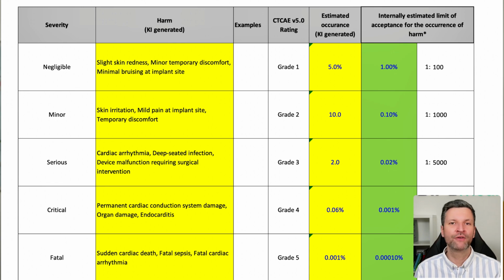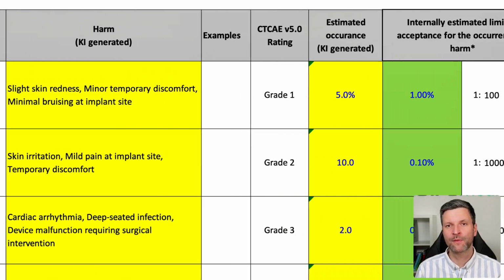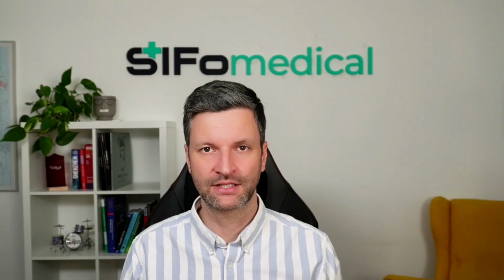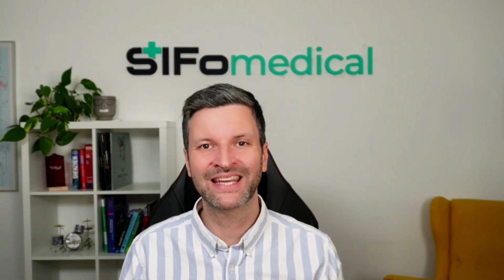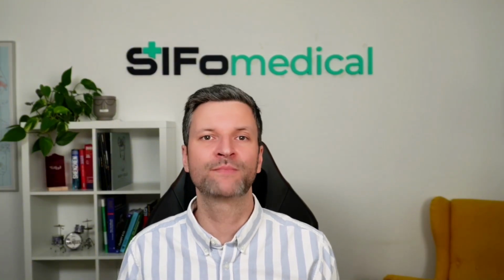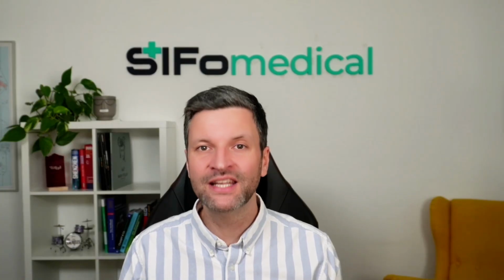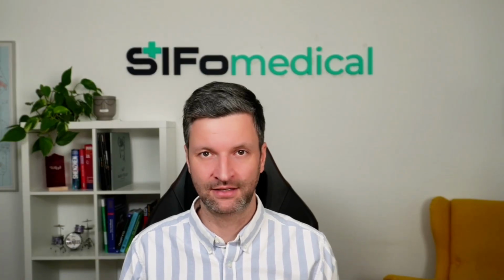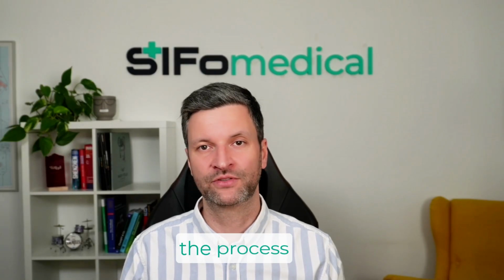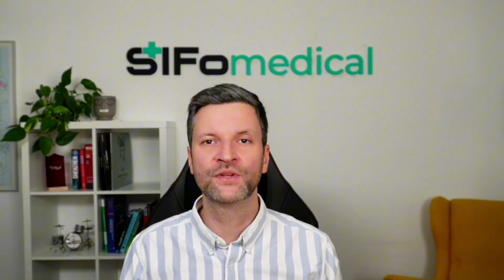Now here's the critical part. Everything the AI generates is a draft. You see suggested hazardous situations, harms, occurrence probabilities, and severity ratings. But you must verify these against your own data, your post-market surveillance data, your clinical evidence, your usability testing. The tool accelerates the process, but you maintain full responsibility.